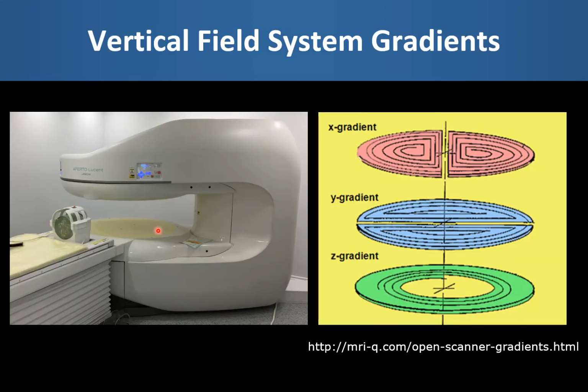Vertical or horizontal field systems have planar gradients built into the pole pieces at the top and bottom. So the vertical Z gradient is a Maxwell pair with currents running in opposite directions, and the X and Y gradients are effectively planar quadrupolar Golay designs. Of course, the gradient performance for these systems is generally inferior to what can be achieved on a superconducting system.